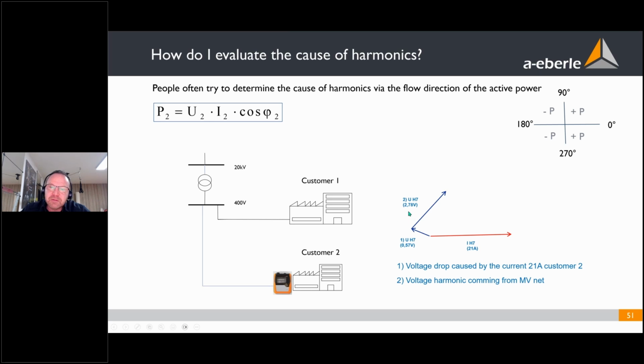From the public grid, we're getting 2.7 volt 7th harmonic. This customer, a big office maybe, is producing also the 7th harmonic with this equipment, but it's different equipment, therefore the phase angle could be in any direction. Our analyzer or any analyzer can only measure what happened here on the voltage. We can't calculate what is the voltage drop of this current. We see what is the result of everything.